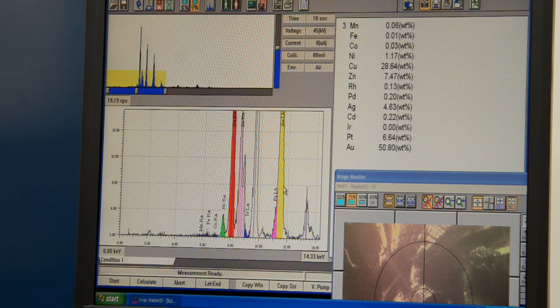So, at first you need the vacuum because you don't have the molecules of air. Right. The electron microscope is giving you the vacuum, and you're not dealing with an X-ray. Oh. So at that point, you're not worried about that X-ray tube being damaged. You're dealing with an electron gun. I see. Okay, and that electron gun is actually hitting the specimen, and that specimen is giving the photons. So I can read that gold sample under vacuum 100 times better. If I do that and it comes out better, I'm going to change my mind about buying a machine. Oh no, not this one, not this one, not this one. This one is incapable of doing that.